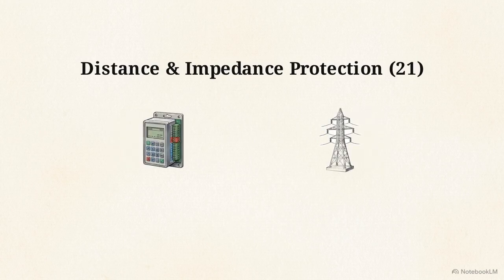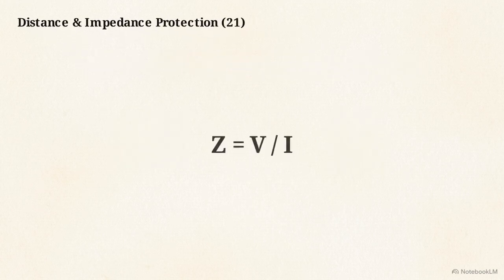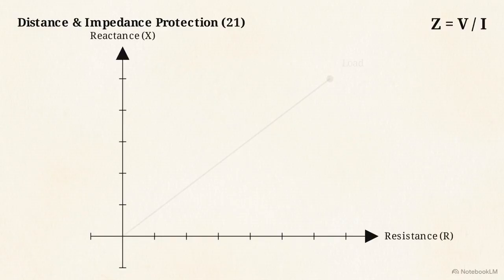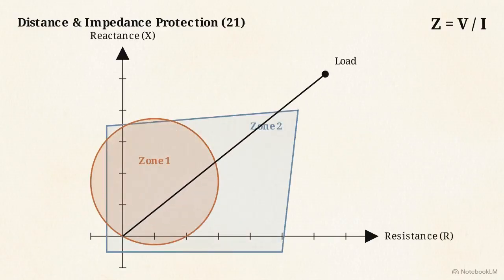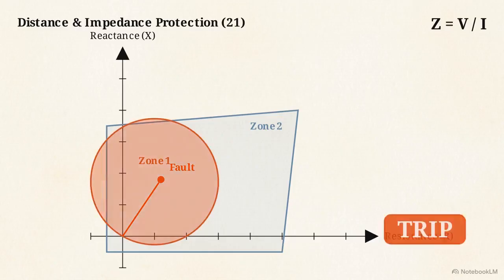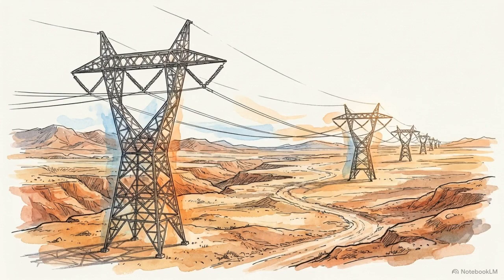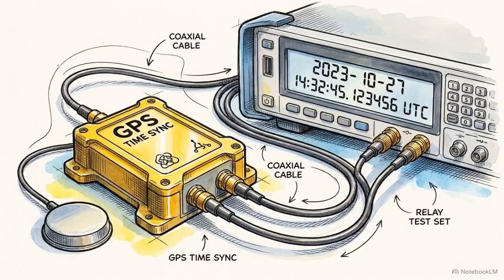Phase C covers distance and impedance protection, or Code 21. These relays calculate fault distance by dividing voltage by current to find the apparent impedance, plotting the results across defined protection zones on an RX plane. Guarding transmission lines that stretch for hundreds of miles requires synchronized equipment. Technicians link their injection sets with GPS time synchronization kits to maintain microsecond accuracy between substations separated by vast distances.